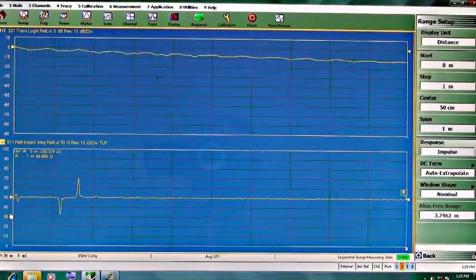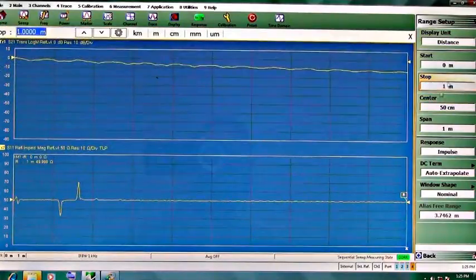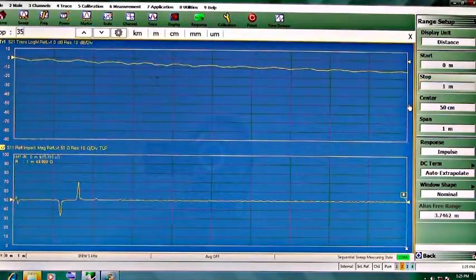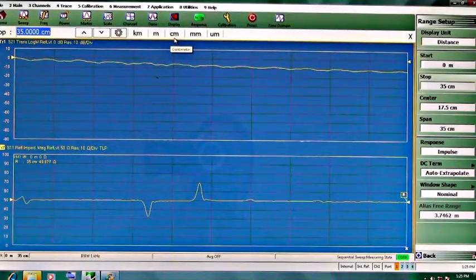You can see now that we have the connector. There is a line length there. Here's two mismatch lines, and then there's some more connection that goes on, and then we're looking way out in the distance. So we'll move our stop to about 35 centimeters. And we're working right now with air dielectric because we use K connectors on the boards. And so this is what it's going to look like with the air dielectric. And this is what we do in impulse mode.